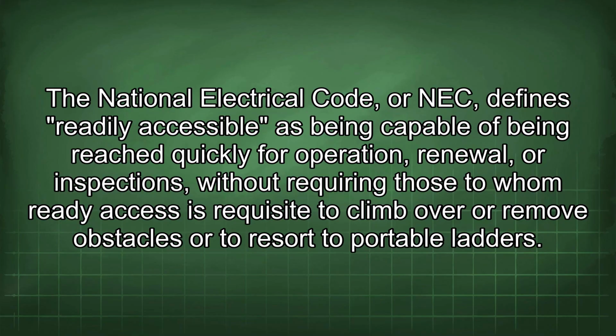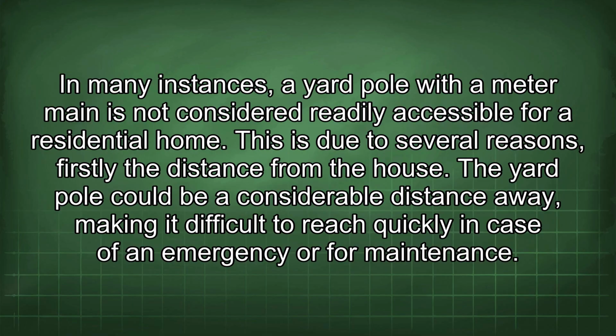The National Electrical Code, or NEC, defines readily accessible as being capable of being reached quickly for operation, renewal, or inspections, without requiring those to whom ready access is requisite to climb over or remove obstacles or to resort to portable ladders. In many instances, a yard pole with a meter main is not considered readily accessible for a residential home. This is due to several reasons.